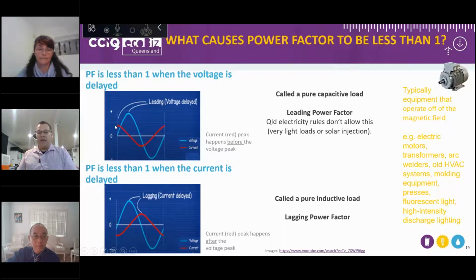As you can see from the slide, leading is when the current peaks before the voltage peaks. Then we have lagging power factor, which is the most common type we see on the network, and largely what customers see when their power factor is less than 1. It happens when the current peak happens after the voltage peak. Typically, what causes a lagging power factor is equipment that operates off a magnetic field: electric motors, transformers, arc welders, old HVAC systems, injection molding equipment, and things like that.